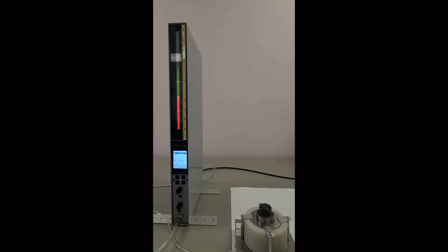The TIR can also be reset automatically rather than using a button if you choose to do so. In this case, you should set the TIR operation to on rather than user, and select a TIR auto reset time from the menu. So we'll go in and look at that. Go into program, down to the utility menu, and down to TIR setup. And you can see here TIR auto reset, the second from the bottom.